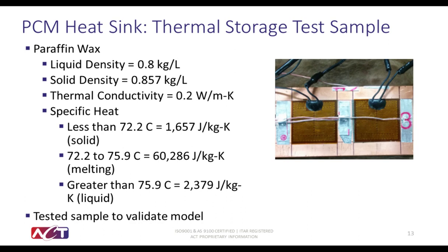The reason PCMs are so effective is that during phase transition, there is a dramatic increase in specific heat. There is an order of magnitude increase from approximately 1,600 joules per kilogram degree Kelvin as a solid to over 60,000 at its melting point between 72.2 and 75.9 degrees Celsius.